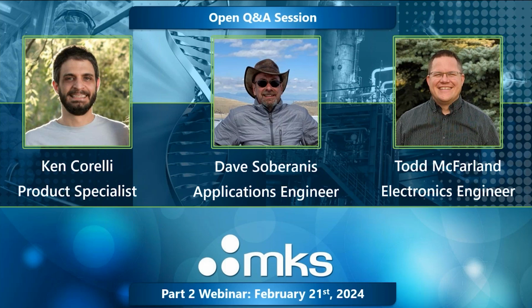Wonderful, thank you. All right, this next person asked, is there a minimal solar cell size that an EQE device can measure? Also a good question. In our EQE solutions, we have a 1 millimeter beam size.